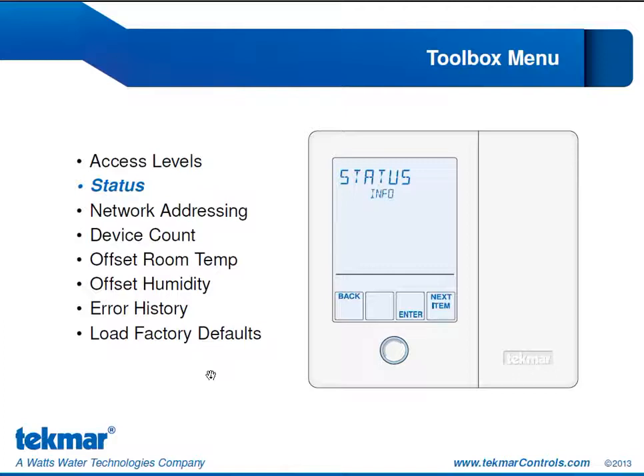Status info is also where we'll see if we're in floor cooling operation, if we're in warm weather shutdown or cold weather shutdown, if we're in optimum start, if we've hit a floor min or a floor max, if hydronic heat has been forced off. And this happens if the 557 as an air group master is in cooling mode and it is holding off that hydronic heat while cooling. It also tells us if we're in the interlock wait period between heating and cooling.